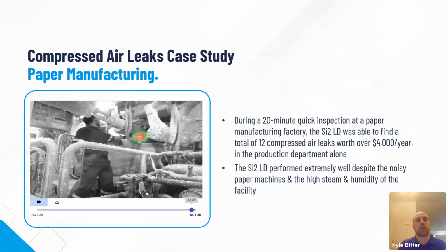Here's a quick case study done by a paper manufacturing company. During a 20-minute quick inspection with the SI2 LD model camera, LD for leak detection, they were able to find a total of 12 compressed air leaks worth over $4,000 in the production department alone. That $4,000 mark represents about 21% of the rough cost of the camera itself, and that's during just a 20-minute survey.